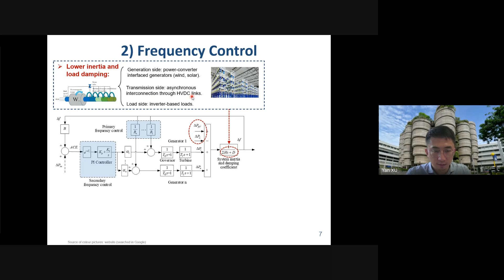And the load, the inverter-based load, they do not have damping either. So you can see that when we have more power converter interface generation, and when we have more inverter-based load, both H and D will decrease. So the system total inertia and damping will decrease, and the system is more sensitive, more vulnerable to power disturbance. In other words, if you give the same power disturbance, the low inertia system will see a larger frequency deviation. Besides the HVDC, they will separate the system into non-synchronous portions, so they cannot support the frequency to each other. That is an issue.